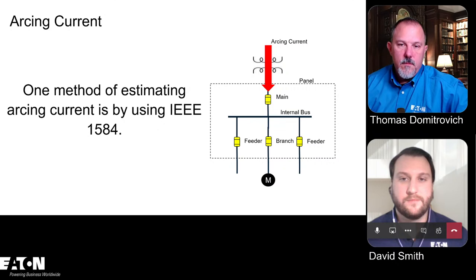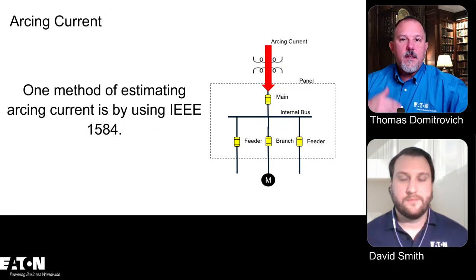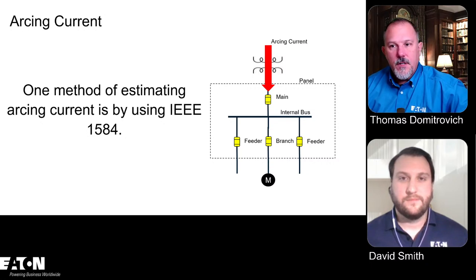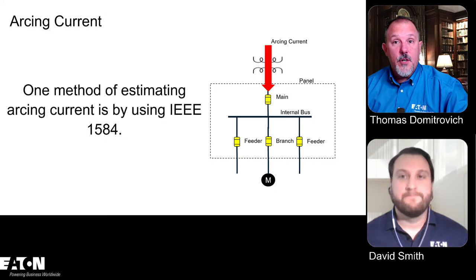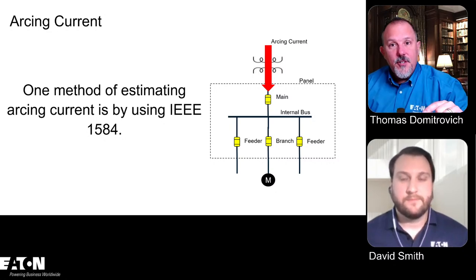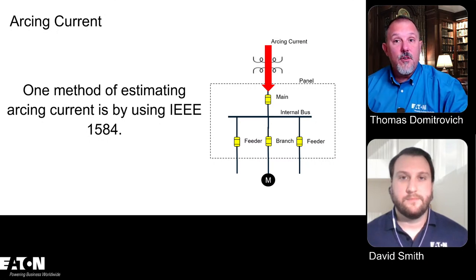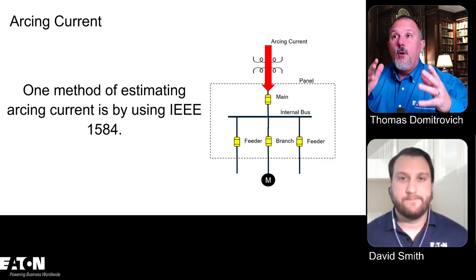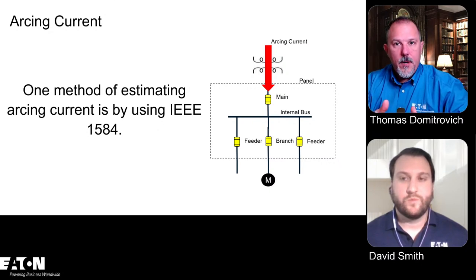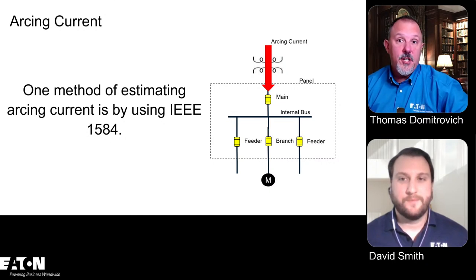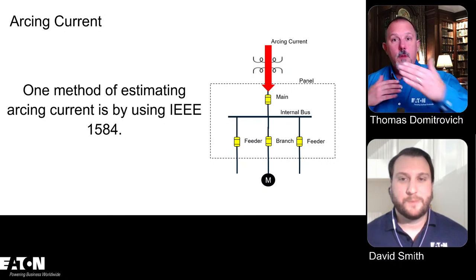Now, the incident energy in this panel is not based upon the clearing time of that overcurrent protective device. The amount of incident energy because of a line side propagation is really based upon the upstream overcurrent device. And the amount of energy is not dependent upon the size of that overcurrent protective device. Because if I have 22,000 amps of available fault current, whether it's an 800 amp breaker or a 1200 amp breaker, if my arcing current is lower than the instantaneous pickup and I'm in, say, a 2 second time delay, in the long time region, I have a lot of incident energy because of the amount of time that I let that energy persist.